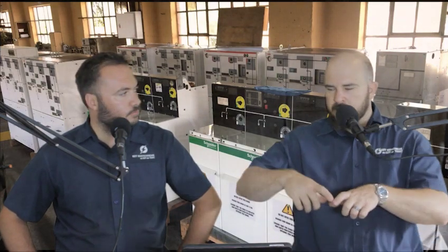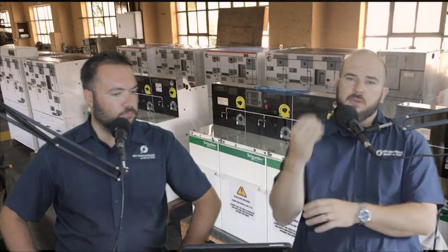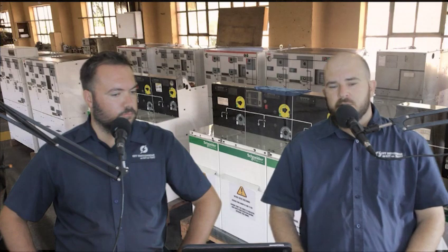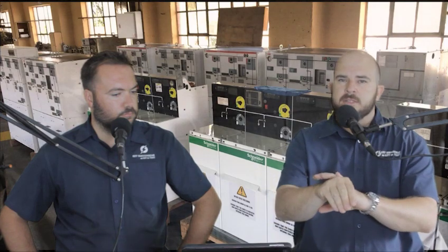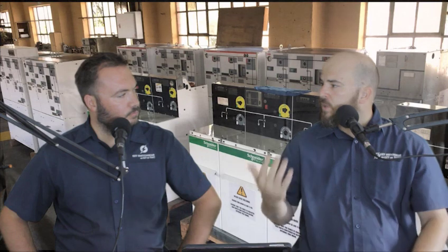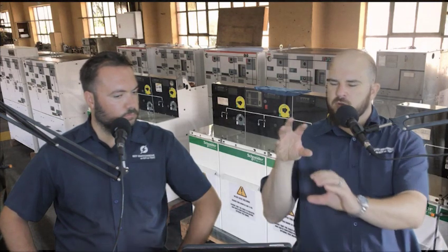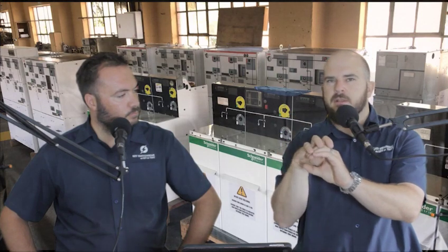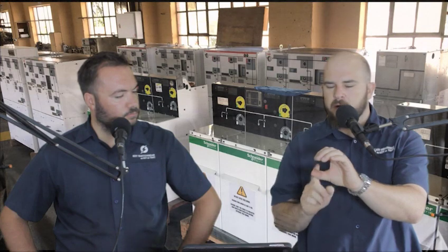The switchgear is either on a trench, or there's core drilling and the cable is coming through the slab or whatever the switchgear is on. And then it connects onto your bushing. The bushing can be inner cone bushings such as in Europe, and then also the outer cone type C bushings, which we normally use in South Africa and in most of the IEC markets. Your switchgear has a plug that goes over that bushing, and your cables have a plug that goes over that bushing where the cable is then fastened on.